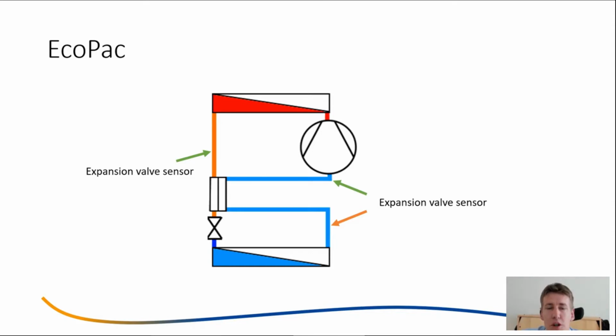Maybe I should say a few words about the system. As you can see, it's a normal heat pump with an extra heat exchanger before the compressor, after the condenser: the internal heat exchanger. The reason we have this is that we use the natural refrigerant isobutane, and we want to make sure that the superheat is high enough so we don't have any oil dissolved in the refrigerant, and that we also gain a bit of efficiency by adding that part.